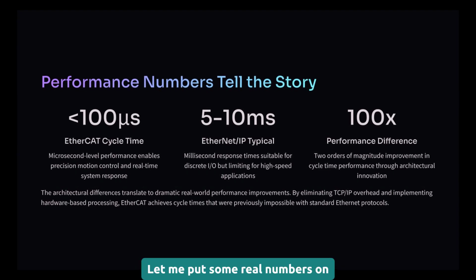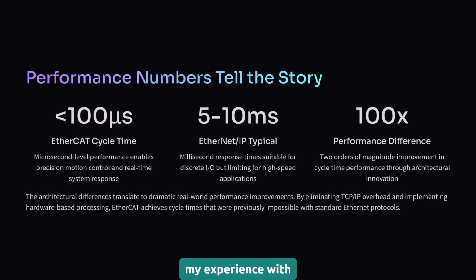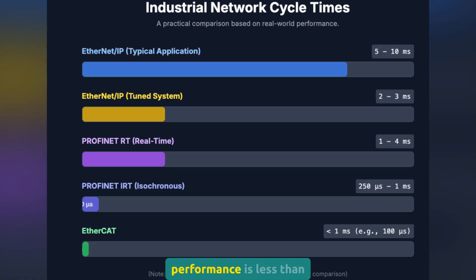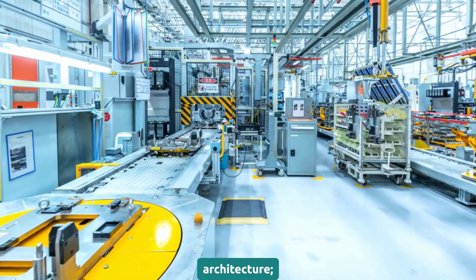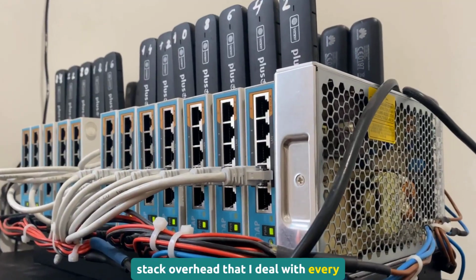Let me put some real numbers on this. In my experience with Ethernet IP, you're typically looking at 5 to 10 millisecond cycle times for standard applications. I've tuned systems down to maybe 2 to 3 milliseconds when pushed hard, but that's about the practical limit with TCP IP overhead. EtherCAT's documented performance is less than 100 microseconds. That's literally 100 times faster than typical Ethernet IP installations. Now, before you think marketing hype, the speed makes sense when you understand the architecture. They've eliminated the protocol stack overhead that I deal with every day.